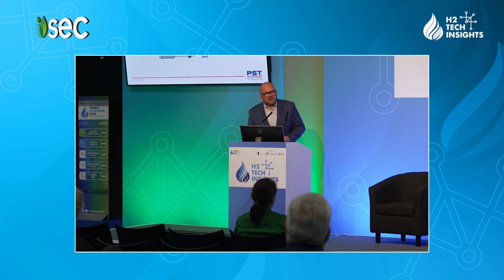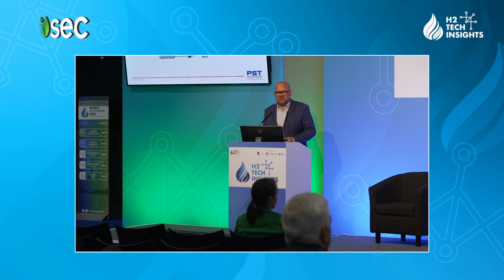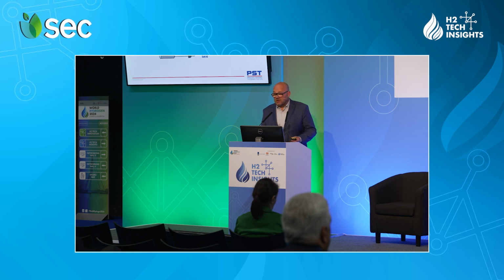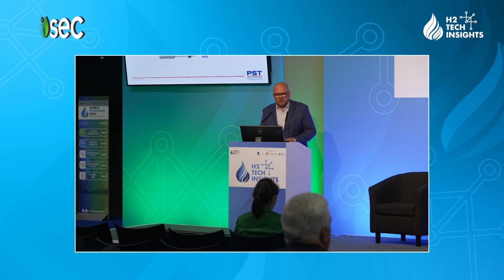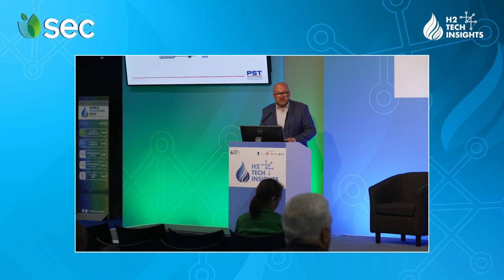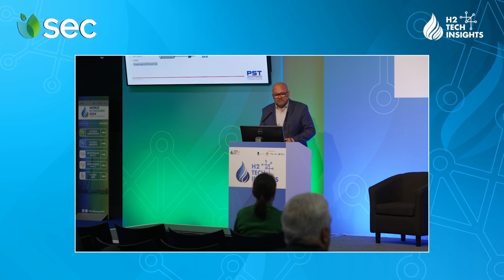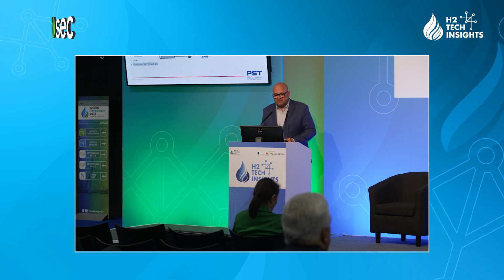So at the cell stack, a lot of things can happen. Seal and connection damage, stack compression can go wrong, contamination from outside if the water is not pure anymore, maldistribution of electrolyte, catalyst activity losses, degradation of the membrane. Actually, a lot of these are related to each other. Maybe even design issues, although you want to prevent that, of course. So that could implicate hotspots, leaks, and especially crossover of hydrogen and oxygen.